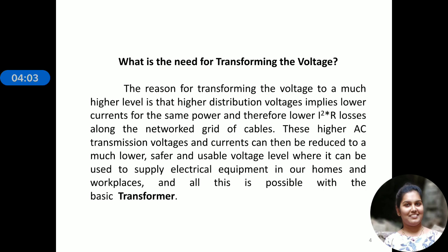The reason for transforming the voltage to a much higher level is that a higher distribution voltage implies lower current for the same power, and therefore lower I square R losses along the network grid of cables.